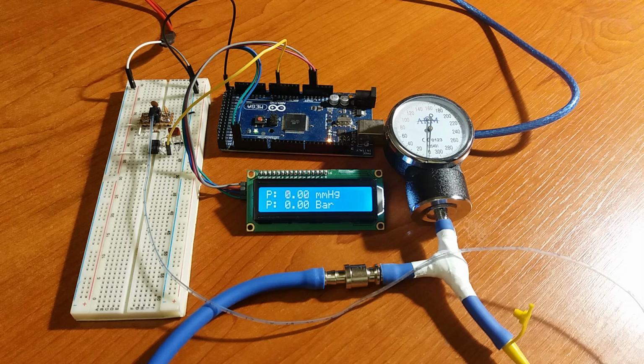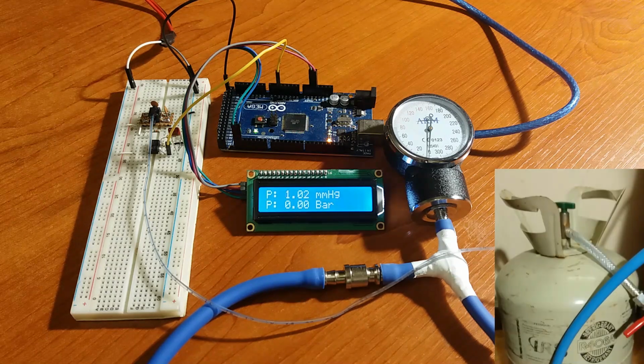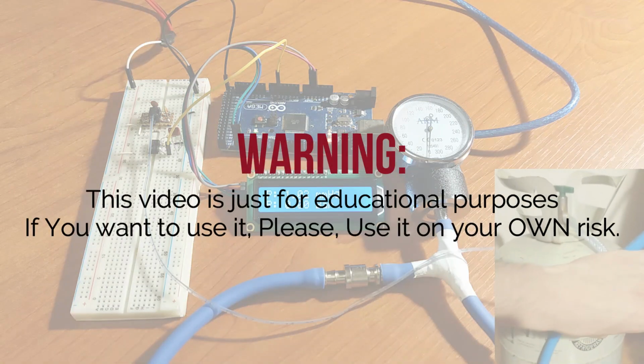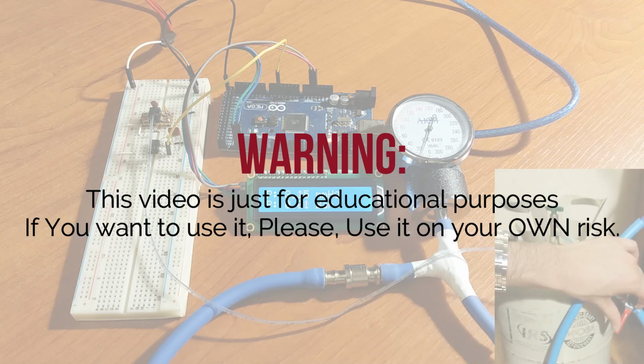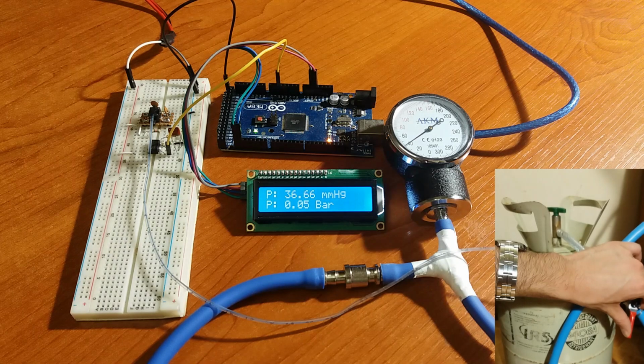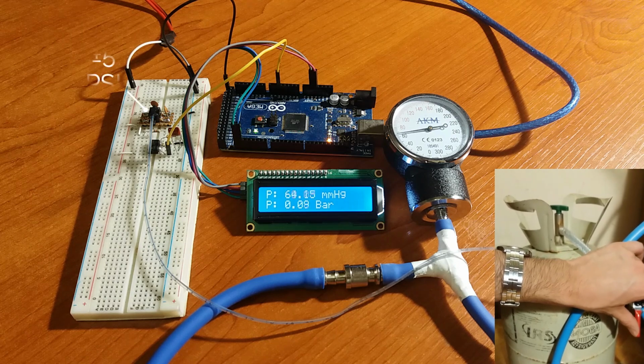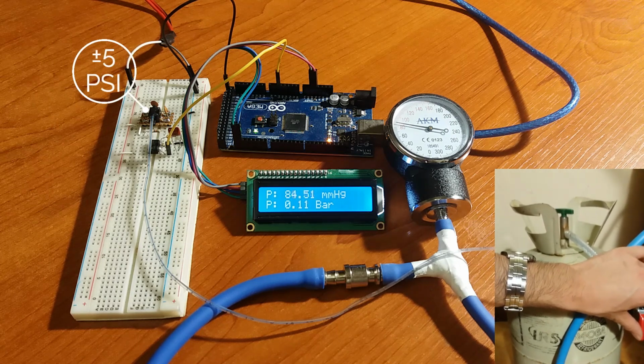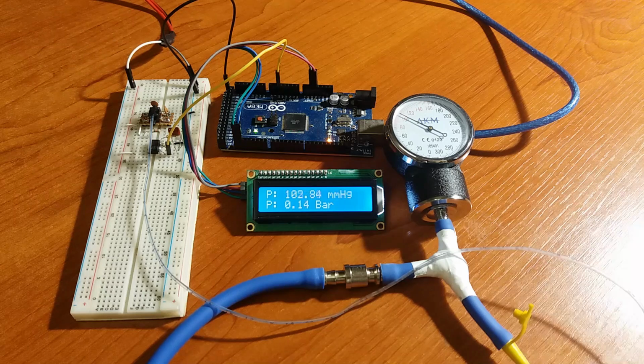In this video, we will see how to use a pressure sensor that uses a Wheatstone bridge to measure the pressures, and we will see the calibration process to get a precise reading from the sensor depending on a known pressure. The concept of this video is simple. Warning, this video is just for educational purposes, so if you want to use it, please use it at your own risk. The sensor that I am going to use has a small measuring range of -5 to +5 psi, since the measured pressure range will be smaller than that, and it will do the job as we intended for either PEEP or trigger or any other goals.